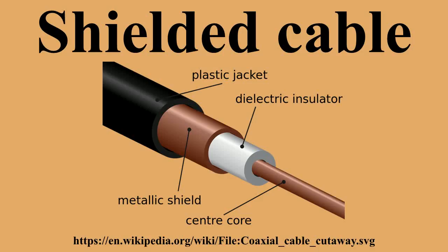The shield minimizes capacitively coupled noise from other electrical sources. The shield must be applied across cable splices. In shielded signal cables, the shield may act as the return path from the signal, or may act as screening only. High-voltage power cables with solid insulation are shielded to protect the cable insulation, people and equipment.